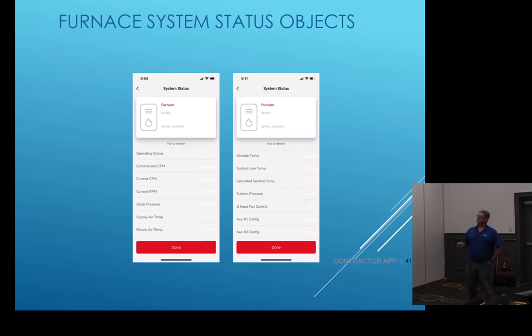So just keep that in mind. It's a great app. Furnaces. Same kind of information you can get off your furnace. I want to say part of the information up here you don't see on this is flame sensor. All of the new furnaces, the flame sensors are digital signal, okay? It's not millivolts like it used to be. You can't take your meter, put it in series, pull that little plug off, that wire off of there, put one lead here and the other lead on that flame sensor and see what the millivolts is going through that flame sensor. Can't do that anymore. It's a digital signal.